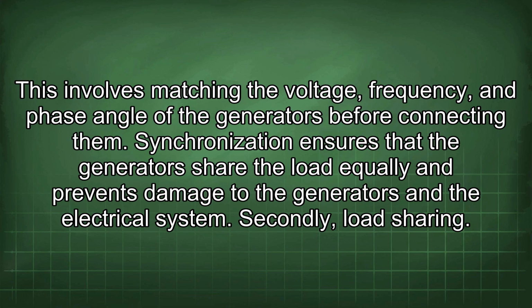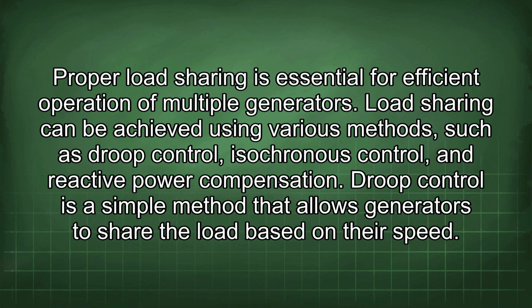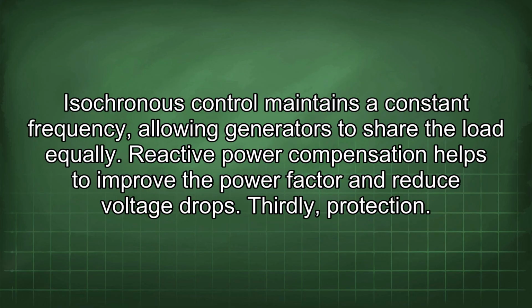Secondly, load sharing. Proper load sharing is essential for efficient operation of multiple generators. Load sharing can be achieved using various methods such as droop control, isochronous control, and reactive power compensation. Droop control is a simple method that allows generators to share the load based on their speed. Isochronous control maintains a constant frequency, allowing generators to share the load equally. Reactive power compensation helps to improve the power factor and reduce voltage drops.